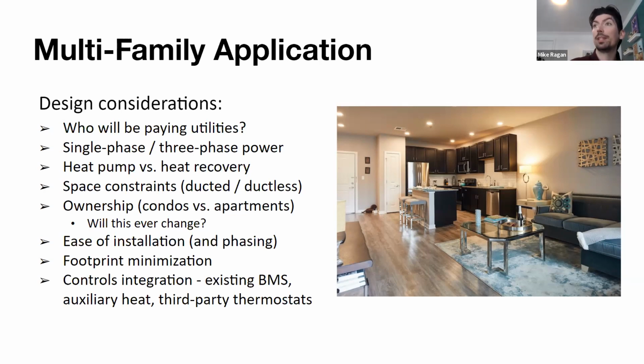From a footprint standpoint, that could also apply to the indoor units. Do you have an existing vertical stack fan coil in a closet where we want to minimize any rework? All right, let's rip that out. Let's put our multi-position ducted air handlers in there. And that's it. That's the indoor unit swap. That's all you need. So definitely going to want to assess the conditions of the space, how much space we have to work with, and what the desired minimizations of footprint are.